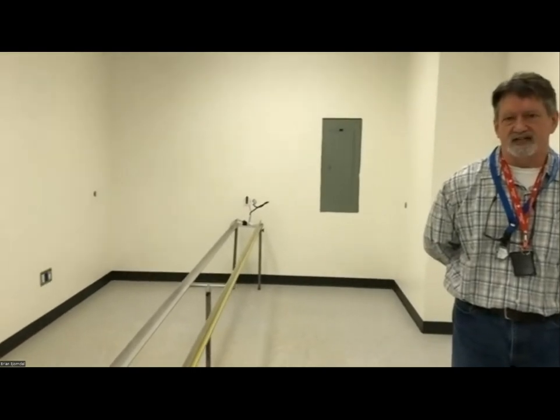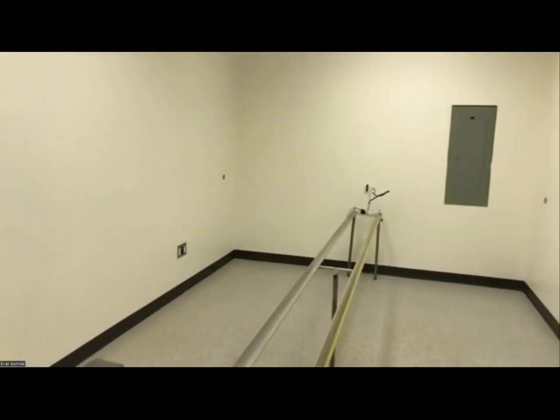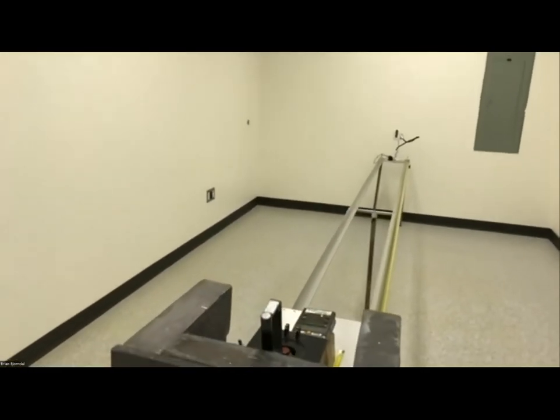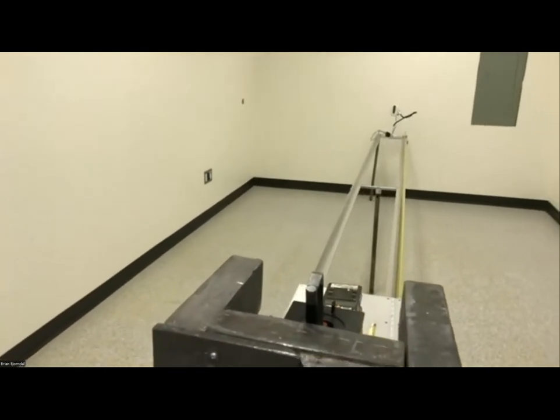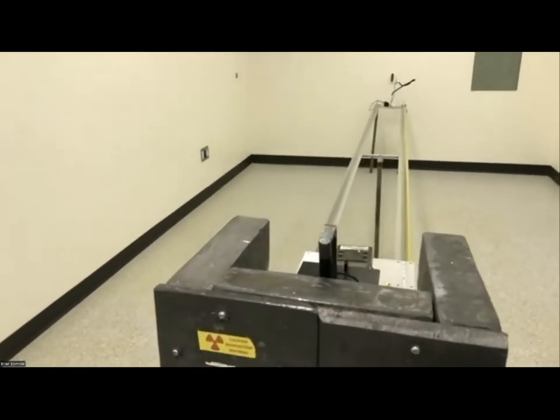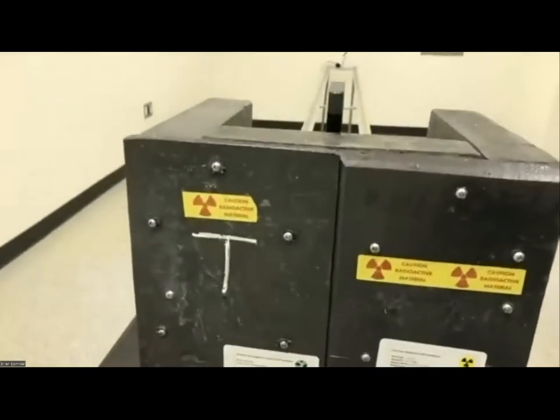So that may not be high enough, and in fact, it likely is not high enough for a lot of moderate survey instruments, unless it's a low exposure rate type of instrument. So no, we don't normally do that. If it's asked, we can try, but at 50 millisieverts per hour, it's not likely we're going to overload it on a lot of instruments.